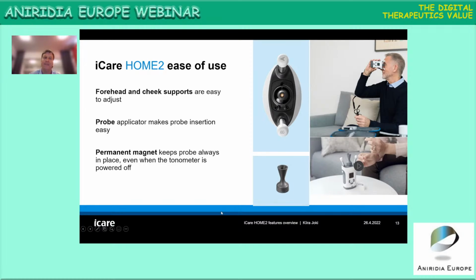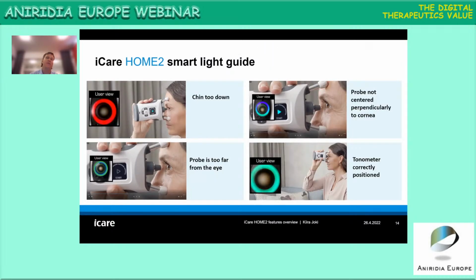And it has a permanent magnet that keeps the probe in place even when the tonometer is powered off. Then, to explain a little bit more about the smart guide, which we consider very important when self-used. If you see a red light in your vision field when you do the measurement, it means your chin is too low and the tonometer is incorrectly positioned.